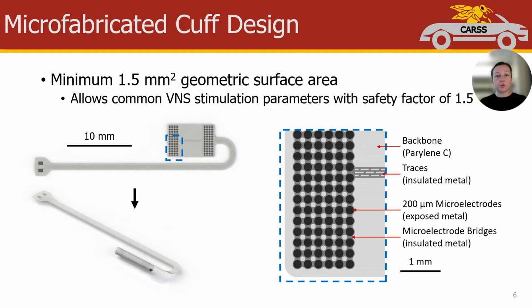Rather than using one large rectangular electrode, we chose to use this aggregate electrode configuration, which consists of an array of shorted microelectrodes that act as a single larger electrode area. The dark gray shows the exposed microelectrodes, the light gray shows the Parylene backbone, and the medium gray shows areas of metal that are insulated by Parylene. This design was selected to prevent delamination and cracking of the thin film metal, which often occurs during chronic stimulation of large exposed thin film metals. The small areas of Parylene to Parylene contact in between microelectrodes, which appear as small light gray dots, help mechanically hold the thin film metal in place to prevent these failures.